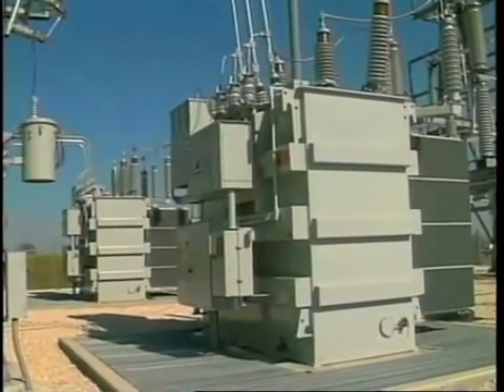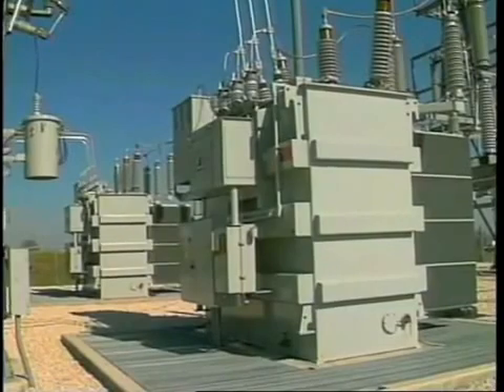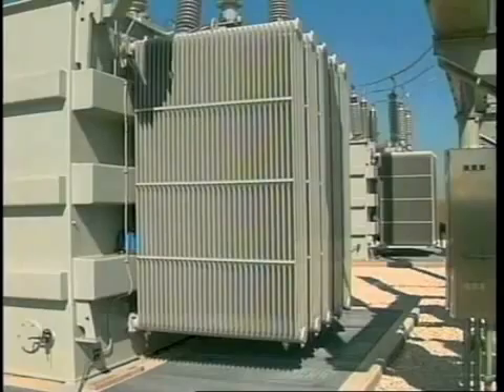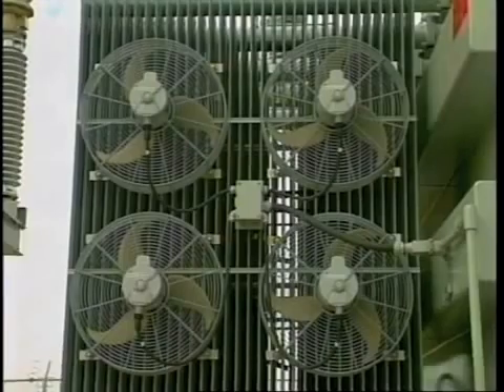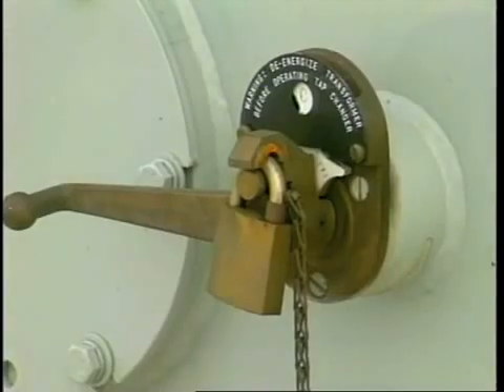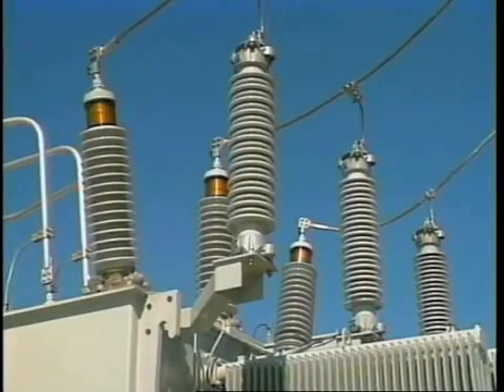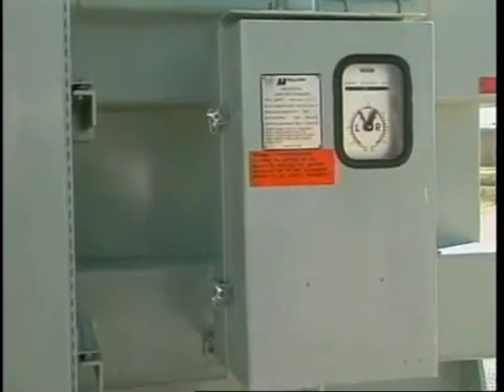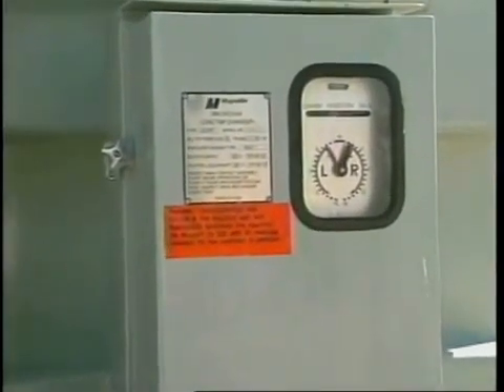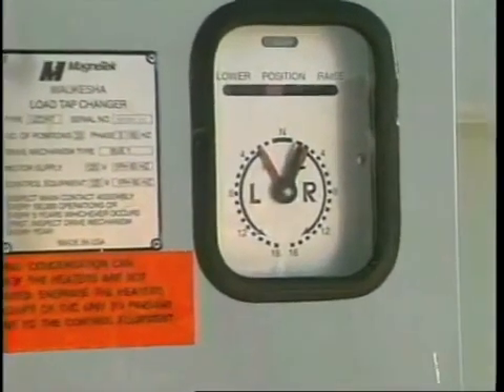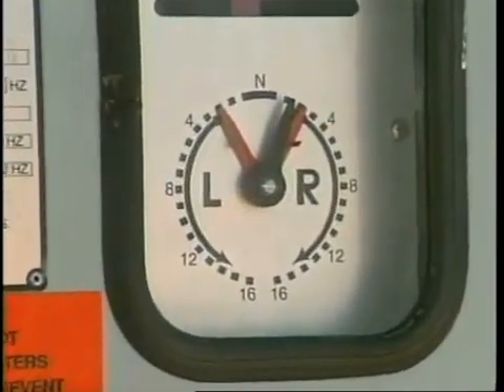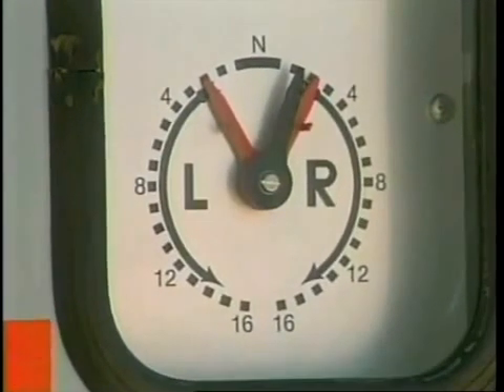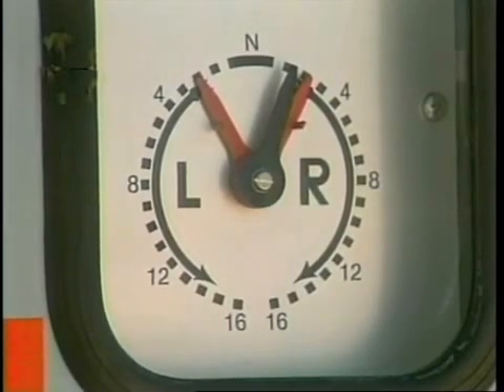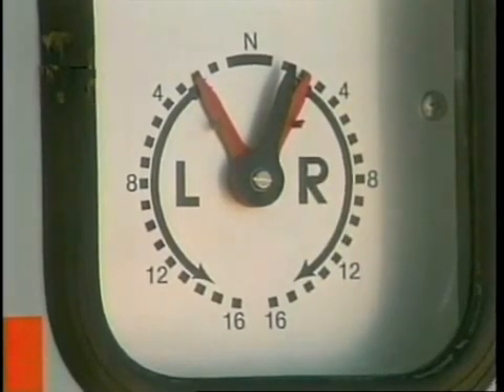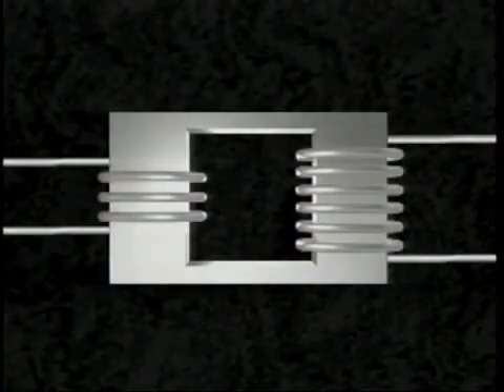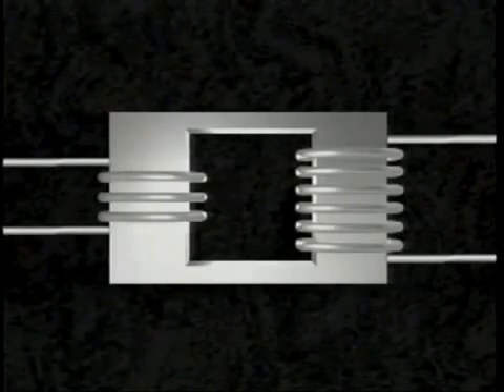The rating of a power transformer depends on its voltage and the load it handles, the way it's cooled, and its auxiliary equipment, tap changers and bushing arrangements. Some power transformers make minor changes in voltage by the use of tap changers. Depending on the application, they can be designed to change voltage for single-phase or three-phase operations. And all power transformers share a basic design.